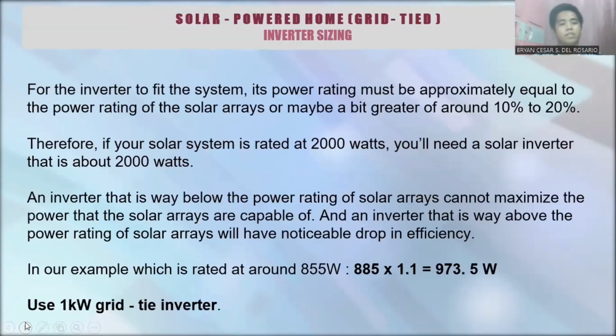Punta na tayo dito sa inverter sizing. Sa inverter sizing naman, for the inverter to fit the system, its power rating must be approximately equal to the power rating of the solar arrays, or maybe a bit greater of around 10% to 20%.